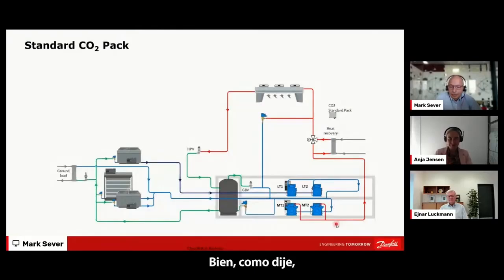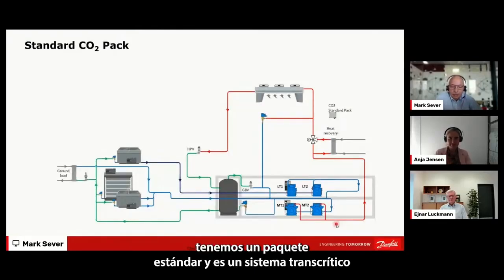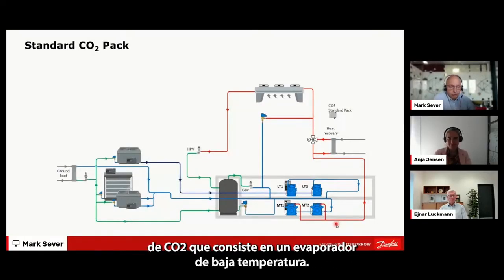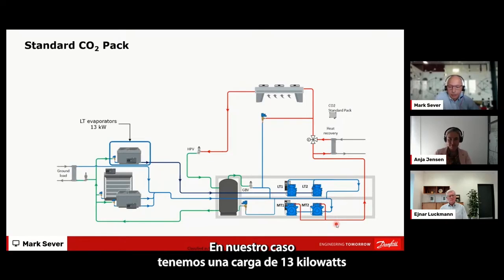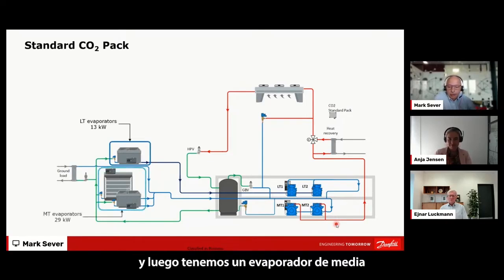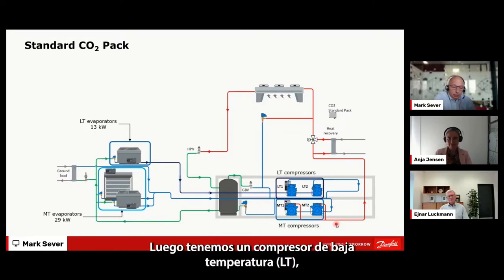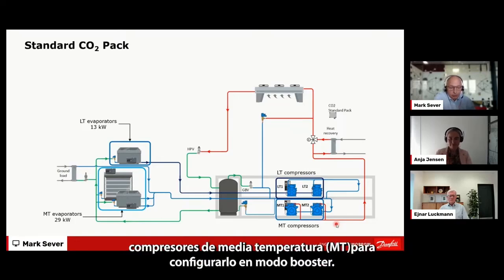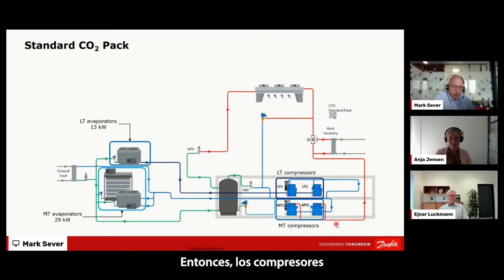Okay, as Einar said, we have a standard pack. It's a standard CO2 transcritical pack consisting of low temperature evaporators. In our case, we have a load of 13 kilowatts there, and then on medium temperature evaporators a load of 29 kilowatts. Then we have low temperature compressors and medium temperature compressors. They are configured in booster mode, so the LT compressors are discharging gas to the suction of the MT compressors.